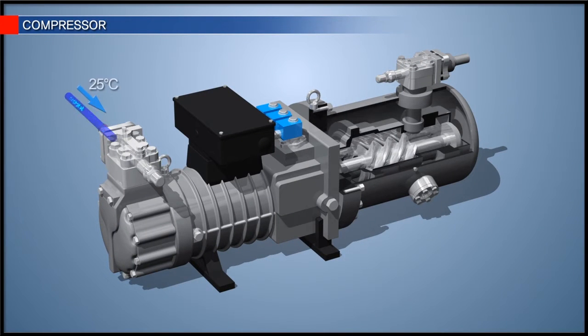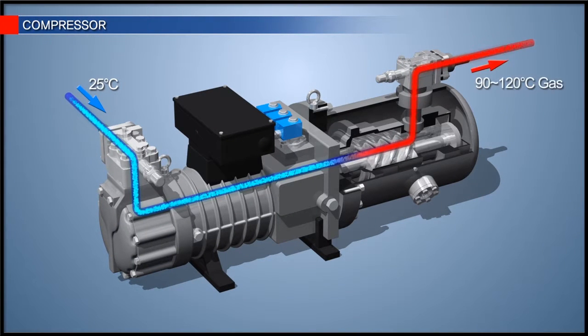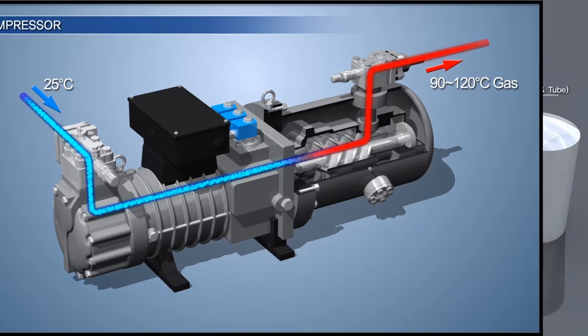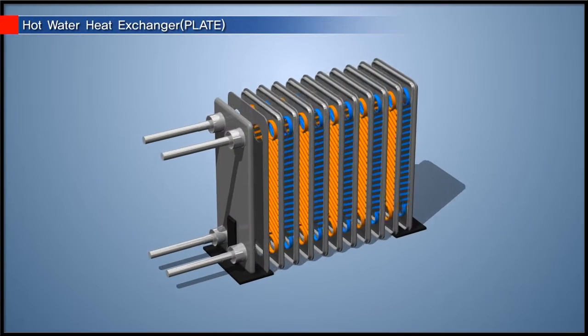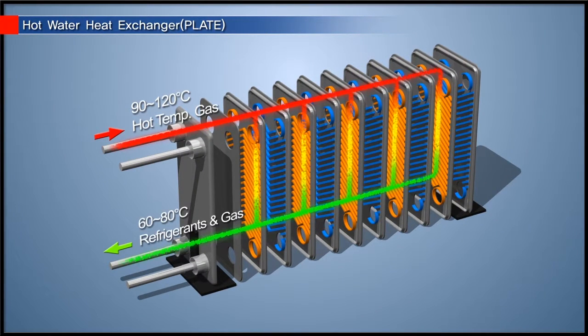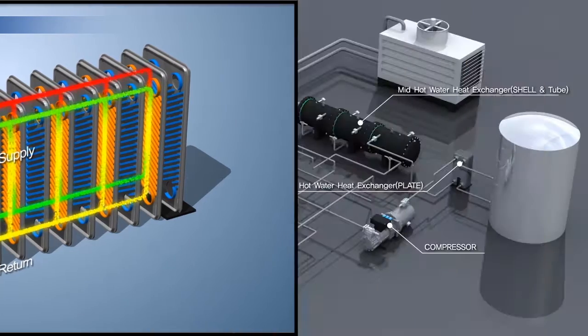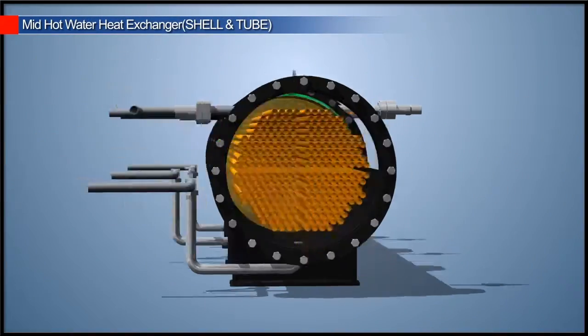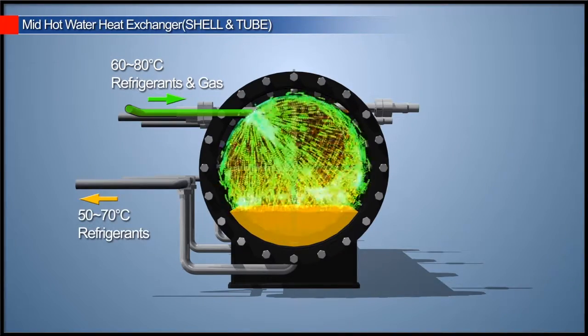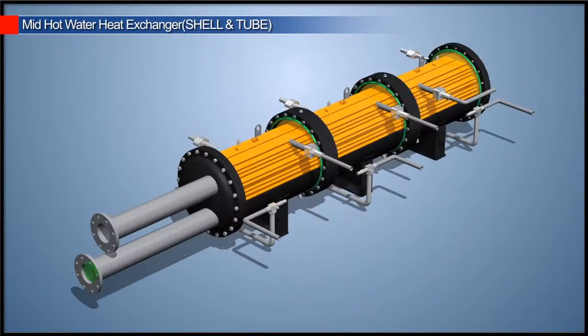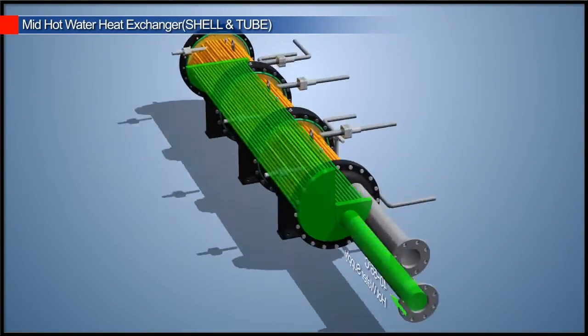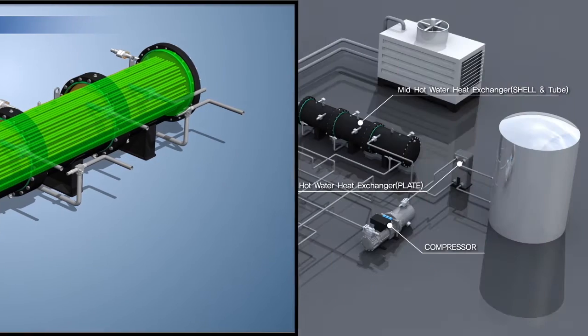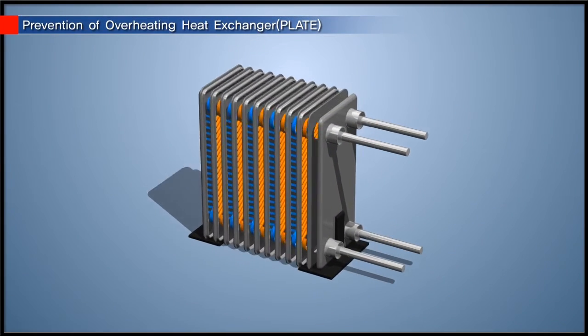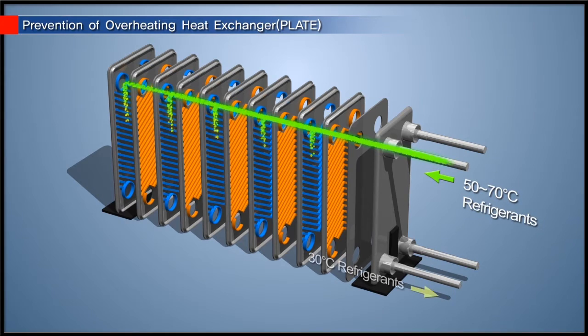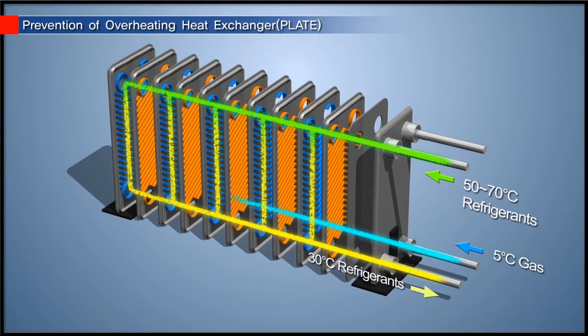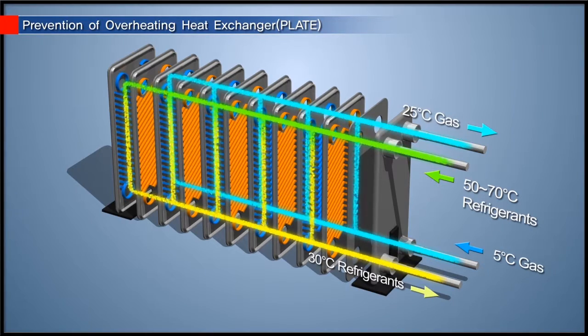First, the compressor compresses 25 degrees Celsius refrigerant gas to 90 to 120 degrees Celsius refrigerant gas. This refrigerant gas produces hot water through the hot water heat exchanger. Through the instant hot water heat exchanger, refrigerants with a lowered temperature of 60 to 80 degrees Celsius go into the hot water heat exchanger and exchange heat to make medium hot water at 45 to 60 degrees Celsius for heating. Refrigerants at 50 to 70 degrees Celsius from the hot water heat exchanger are circulated within the anti-overheat heat exchanger to be cooled down to 30 degrees Celsius.